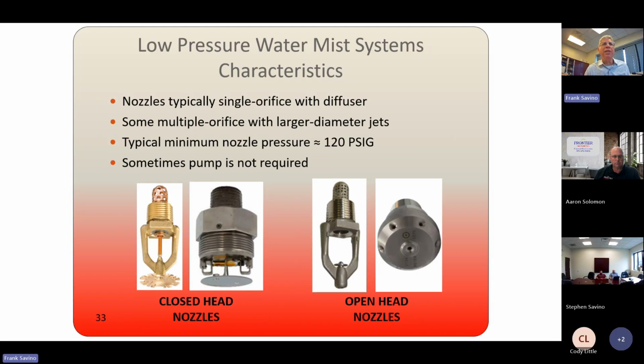Okay, these are some low pressure mist nozzles that you see here. Typically, you also have that orange fusible element that I'm pointing to here. That's the part that breaks in the fire. It's a single orifice with a diffuser on this particular arrangement here, very similar to a regular sprinkler head. What you see at the top here is a screen that's designed to prevent any particulate matter from blocking the orifice of the nozzle. And that's one thing with water mist systems, being that you have a smaller orifice, that you have to really pay attention to, and that's filtering the water to prevent an orifice from being clogged.